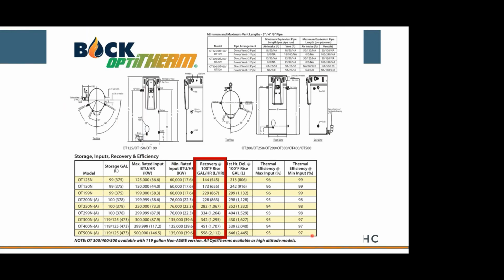So if you're looking at recovery rates, one thing about water heaters, it's usually in gallons per hour. Everything else we do in the hydronics business tends to be gallons per minute, but water heaters are gallons per hour. So in this case, you'll notice a little 125,000 BTU gas-fired tank-type water heater can recover 144 gallons a minute. Or sorry, gallons per hour. See, there I go again. And if you take 144 divided by 60, that's equivalent of about 2.4 gallons per minute.